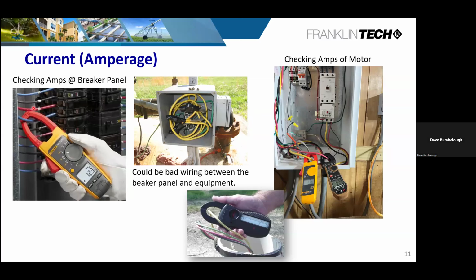So we can start where the power supply comes in, and then go to the next junction point, and then the next junction point, and even down to the well itself to try to isolate where that leakage is. Because if we have something tapped off at a junction box after the breaker here, that, along with whatever's running downstream of it, will add up at the breaker. Okay, so we can just do a process of elimination. Let's just keep on going down the line until we find out where that extra is coming from.